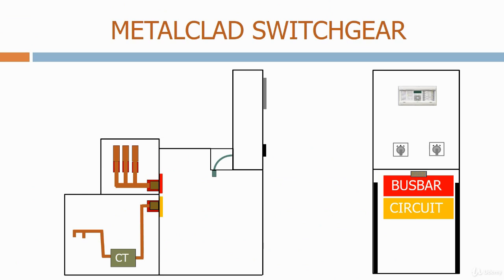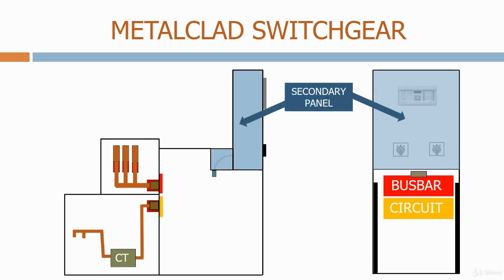The truck goes into a main enclosure, which connects all of the main bus bars and other circuits together. This has numerous metal enclosed chambers, all electrically segregated from each other, so that if a fault occurs in one chamber, the damage does not extend to other parts of the housing. The first chamber is the secondary panel. This is normally on the front of the Metalclad enclosure and contains all of the protection relays, operational switches, and secondary circuits for tripping, closing, and monitoring the circuit breaker.